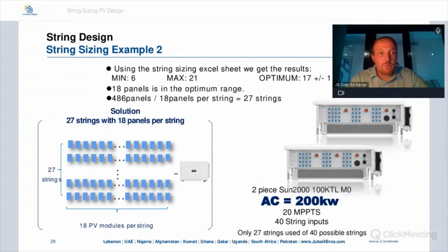So remember, we want 485.9 panels. So you play with these numbers and see what number can divide evenly to make it standard. What we get is 18 panels. 18 times 27 is 486. So that's perfect, that's what we're going to use: 18 panels per string, and we have 27 strings. 18 times 27 is 486 panels. That matches what we targeted.